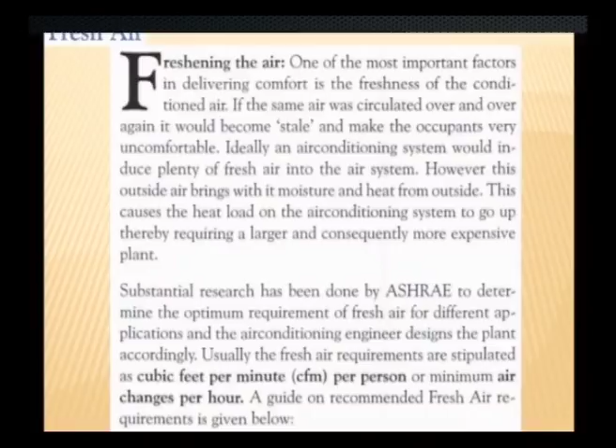However, this outside air brings with it moisture and heat from outside. This causes the heat load on the air conditioning system to go up, thereby requiring a larger and consequently more expensive plant. Substantial research has been done by ASHRAE to determine the optimum requirement of fresh air for different applications, and the air conditioning engineer designs the plant accordingly. Usually, the fresh air requirements are stipulated as cubic feet per minute (CFM) per person, or minimum air changes per hour. Let us look at the guide on recommended fresh air requirements.